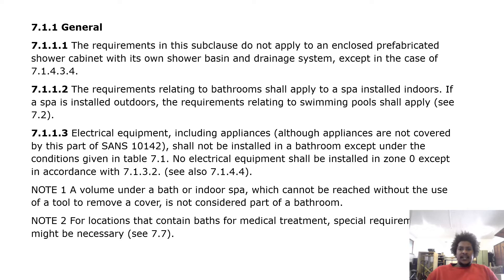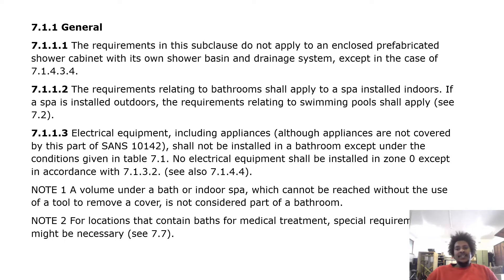Electrical equipment, including appliances — although appliances are not covered by this part of SANS 10142 — shall not be installed in a bathroom except under the conditions given in Table 7.1. No electrical equipment shall be installed in zone 0 except in accordance with 7.1.3.2. Note 1: a volume under a bath or indoor spa which cannot be reached without the use of a tool to remove a cover is not considered part of a bathroom. Note 2: for locations that contain baths for medical treatment, special requirements might be necessary.